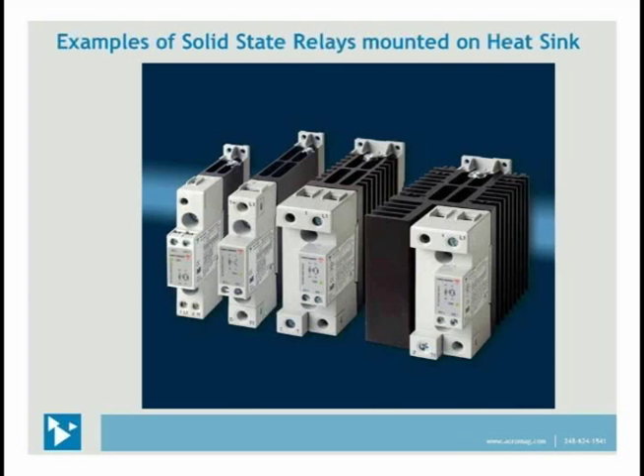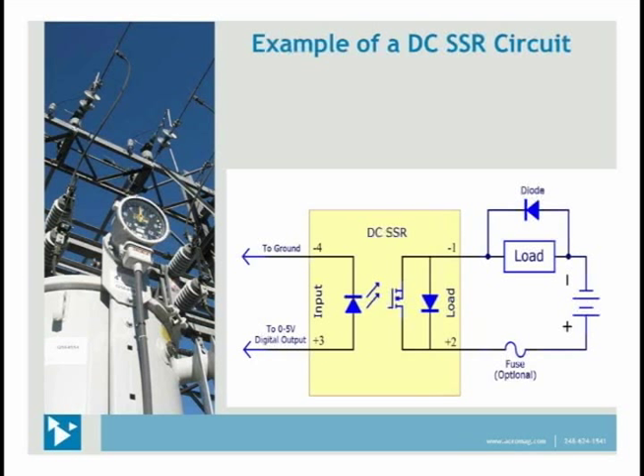Now, some types of solid-state relays have polarity-sensitive output circuitry, while electromechanical relays are not affected by polarity. Solid-state relays have a tendency to fail shorted on their outputs, while electromechanical relays tend to fail open. Many solid-state relays have optocoupling, which allows the control circuits to be electrically isolated from the load. In this slide, we see that a control voltage energizes an LED. The LED becomes illuminated and switches on a light-sensitive diode. The diode's current then turns on a back-to-back thyristor, SCR, or MOSFET to switch the load.